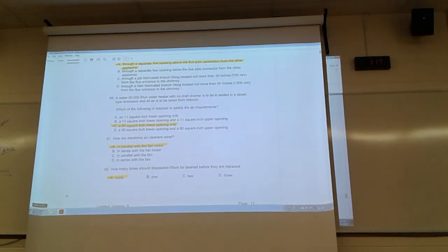What size opening do you need? 60 square inches, lower opening only, C. Okay, the same scenario, the air is in the house, and the air that's in the house has to get into the closet, so you've got to have an opening. How big should the opening be? 1 square inch for every 1,000 BTUs.